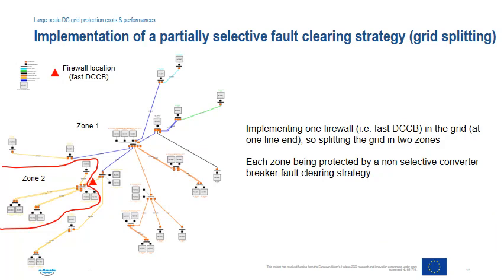Implementing partially selective protection strategies based on splitting the grid into several protection zones could be a solution to reduce the potentially higher impact on the AC system of non-selective strategies. One such grid splitting approach was considered by implementing a firewall device, a fast DC circuit breaker, at one line end of the grid, thereby splitting the grid into two protection zones as shown here. Each zone is then protected by a non-selective converter breaker fault clearing strategy.